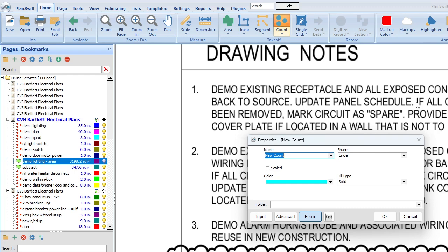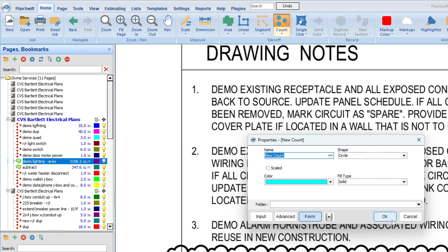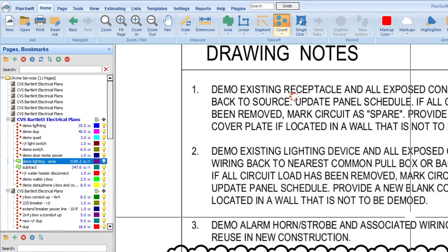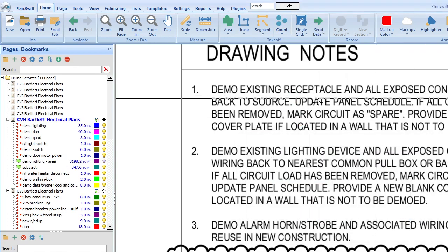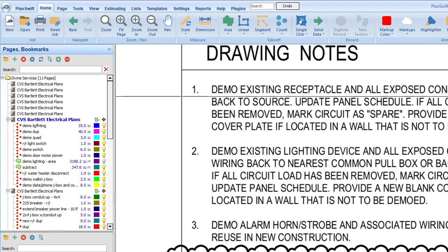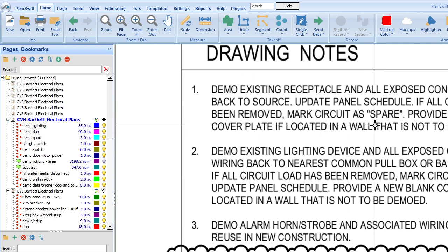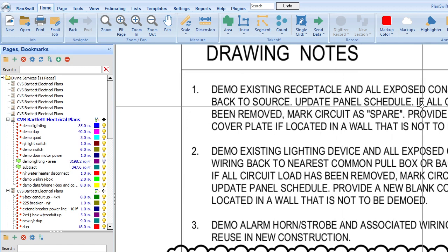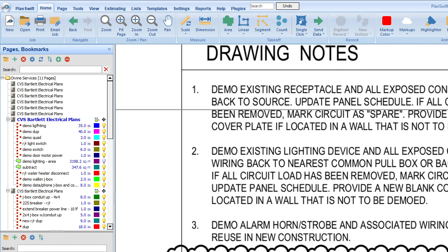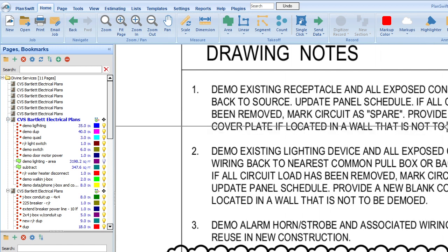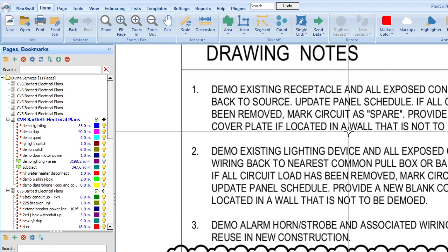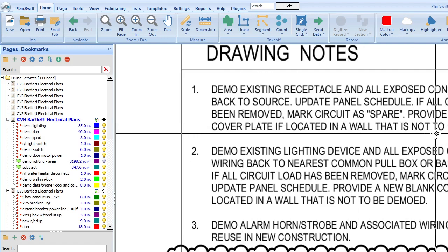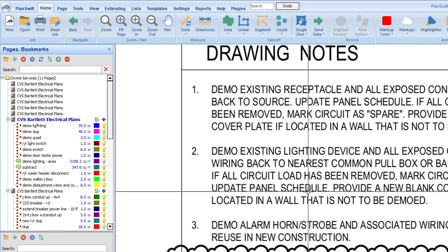Like update the panel schedule. If you're new, you may want to do that. But rule of thumb for me is when we have a renovation, we do what's called balance the panel. And so we give time for replacing all of the breakers that are there, reconfiguring the breakers. So it depends on the size of the panel. So we say balance the panel. That includes that. But then it also includes updating the panel schedule. And so I don't need to count for this in this case. But that's something you want to think about from my years of doing this. If it's not graphically represented in the plans, it's written in the words somewhere. And so you have to account for it. You have to make sure you don't forget it. And so that's one way. But again, you do it enough, you know when you balance the panel, you have to update the panel schedule. So I don't need to make that something that I count. So I make sure I don't forget.